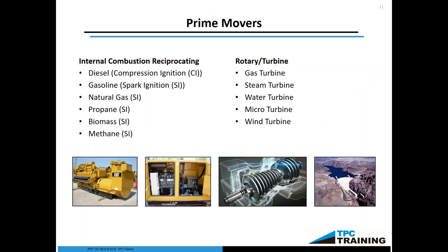Other types of prime movers include internal combustion reciprocating, rotary, and turbine. Rotary and turbine are the most efficient, hence why they're primarily used in prime power. However, rotary and turbine generally take time to speed up — like a gas turbine, it takes a good 50 seconds or so to spin up and take the load. Internal combustion is cheaper, but it's also more maintenance intensive. In general, any type of turbine is more efficient than any type of combustion, and that is also why turbines are typically associated with prime power as opposed to standby power.